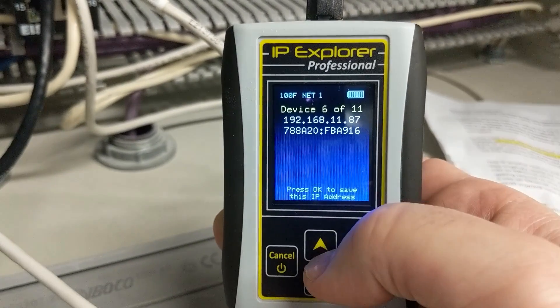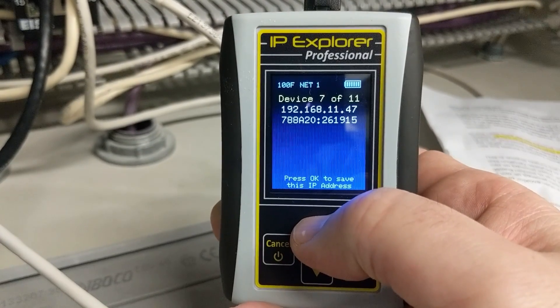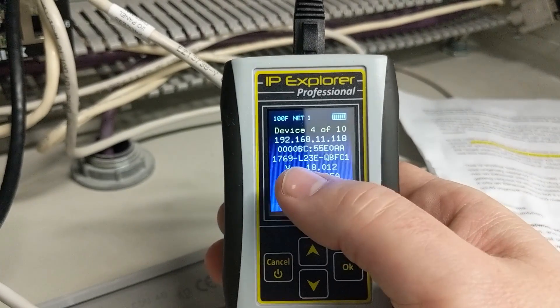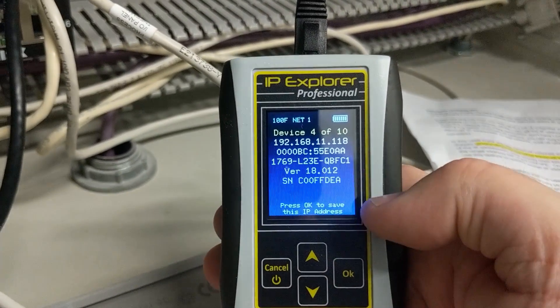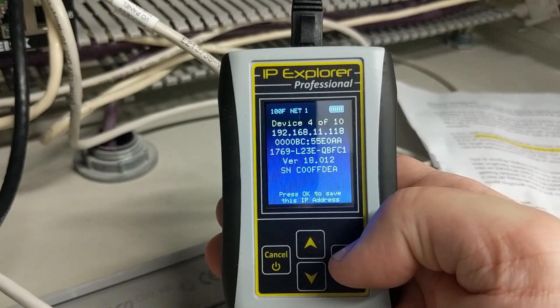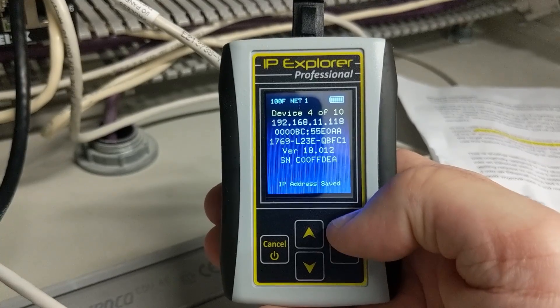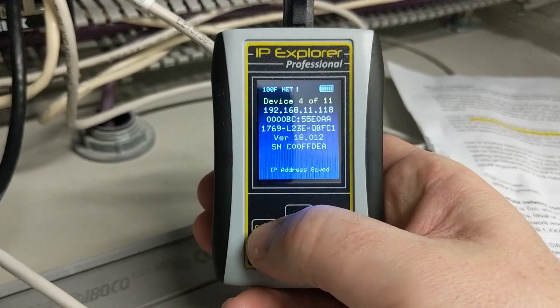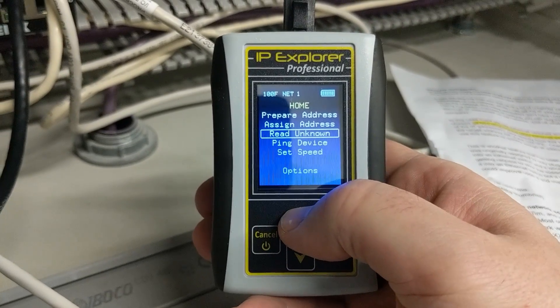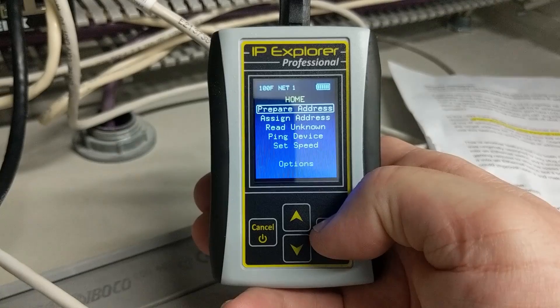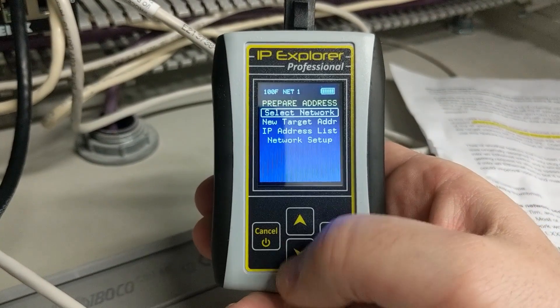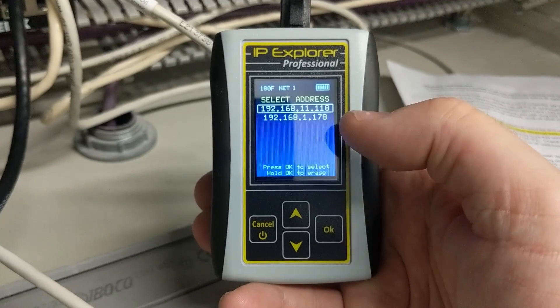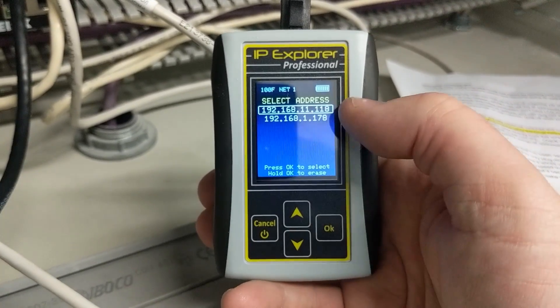This device here is just going to give us its IP address. Also from this screen, let's say we needed to replace this 1769 L23E — we can add it to our target IP address simply by pressing the OK button. That way, once we go out of here and go to assign an IP address, we prepare it and go to our IP address list where we can select what we're going to assign to our new device. You see it's right there.